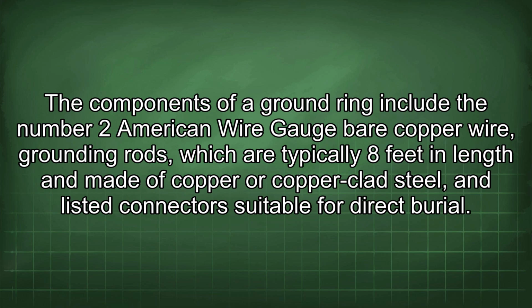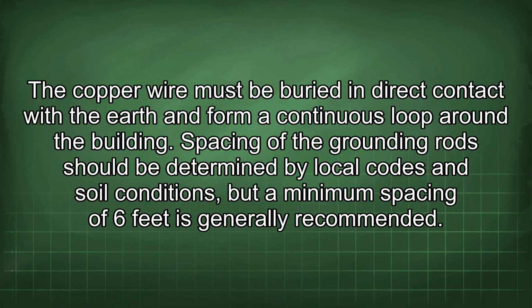The components of a ground ring include the number 2 American wire gauge bare copper wire, grounding rods, which are typically 8 feet in length and made of copper or copper-clad steel, and listed connectors suitable for direct burial. The copper wire must be buried in direct contact with the earth and form a continuous loop around the building.